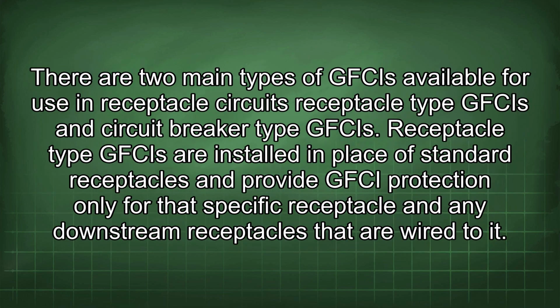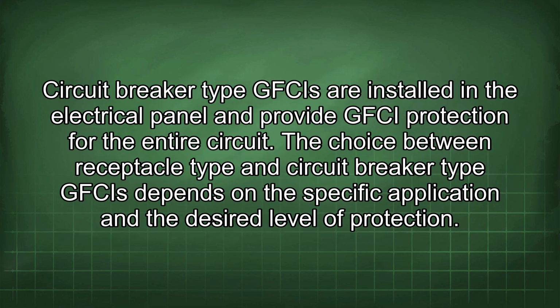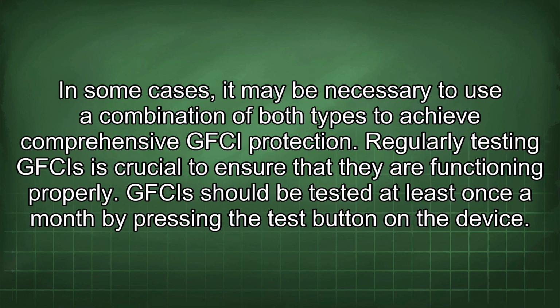There are two main types of GFCIs available for use in receptacle circuits: receptacle type GFCIs and circuit breaker type GFCIs. Receptacle type GFCIs are installed in place of standard receptacles and provide GFCI protection only for that specific receptacle and any downstream receptacles that are wired to it. Circuit breaker type GFCIs are installed in the electrical panel and provide GFCI protection for the entire circuit. The choice between receptacle type and circuit breaker type GFCIs depends on the specific application and the desired level of protection. In some cases, it may be necessary to use a combination of both types to achieve comprehensive GFCI protection.